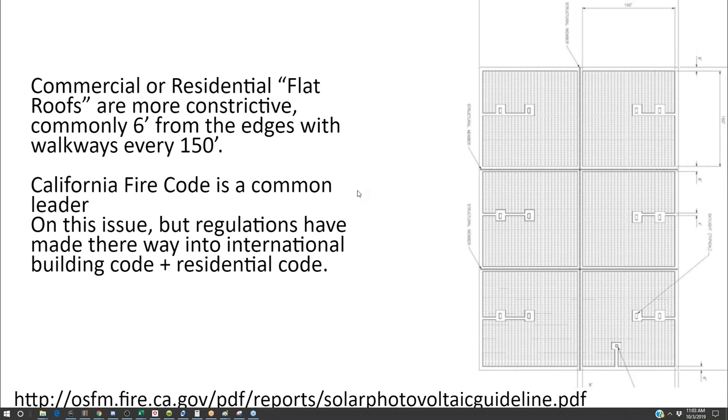These fires occurred for a few reasons. Most solar installers know that old-school combiner boxes combined with old-school inverters, which had a negative grounding in their ground fault protection, had a blind spot. If a fault occurred on the rooftop under a very particular freak circumstance, it would trigger a cascading effect where the combiner box would become a weak point and cause all the circuits to ground fault.